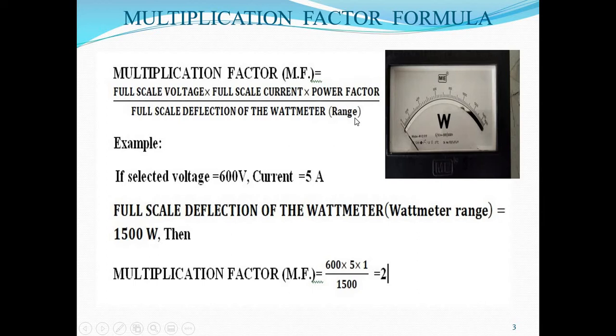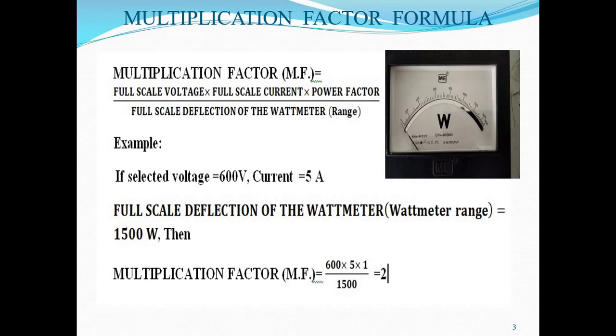The basic theoretical formula for calculation of the multiplication factor is: multiplication factor equals full scale voltage into full scale current into power factor, divided by full scale deflection of the watt meter — that is, the range of the watt meter. For this watt meter, 0 to 1500, so 1500 is the watt meter range. Regarding power factor, unless stated otherwise, you need to consider power factor equal to 1 every time.